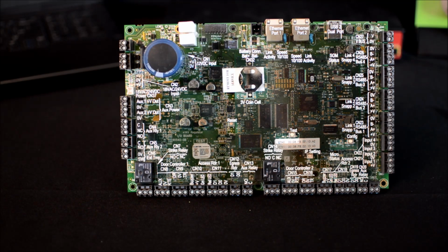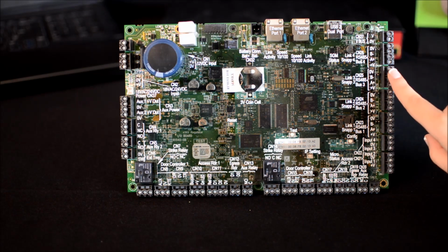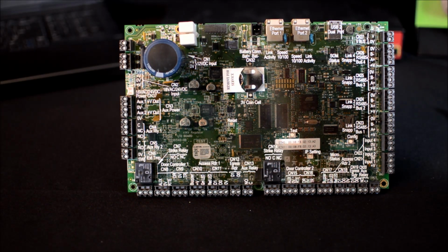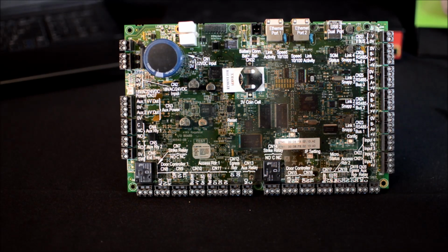Moving up the panel from CN22, we see the first of 4 RS-485 communication bus terminals. These terminal blocks allow for the wiring of auxiliary downstream devices such as additional 2-door controllers or input-output boards. The snap bus wiring is referred to as 2-wire 485. 2 conductors are required for communication and 2 conductors are required for power. The downstream modules can be powered by external power supplies. Best practice regarding 485 wiring recommends that all modules on the bus share a common ground.